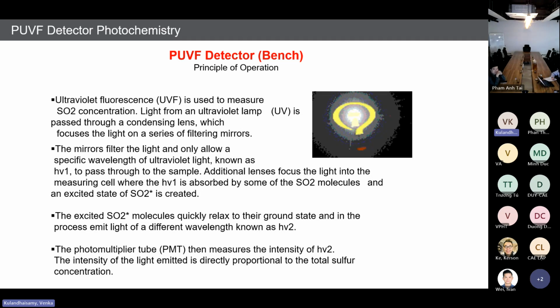So the UV lamp will flick like this and then off. Whenever it's lighting up, it will emit the UV light at the particular wavelength to energize the SO2 molecules. Whenever it goes off, the molecules will de-energize and then emit photons.